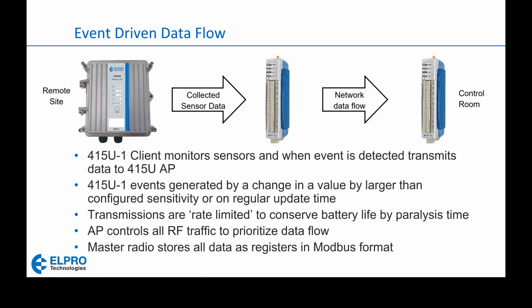And the discrete inputs are monitored continuously. Because it requires extremely little power to monitor the status of a discrete input, we monitor these discrete inputs continuously. And if any discrete input changes state, that value is then radioed immediately to this repeater and then back to the control room. So the response time on discrete inputs is virtually instantaneous. The response time on analog inputs, well, that's a little more complicated because we have to power up the sensor, we have to take a reading, and we have to send that across. So it consumes a little bit more power. But we do have that sample time every 10 minutes or so. That's when the radio is going to power on the loop, take a reading, and see if there was any change. And if there was, go ahead and transmit that over the air. So that's generally how we work.